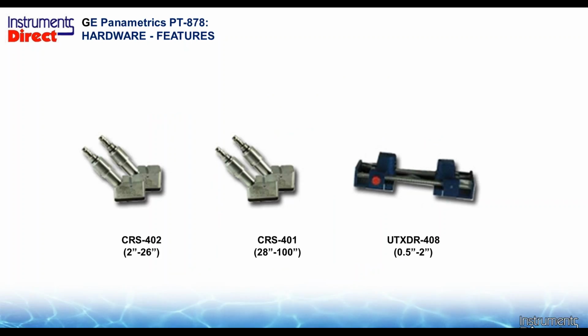Transducers, we have a host of different transducers for this particular model, and the transducers are selected primarily by pipe size. And I think that's a defining point between the PT878 and the bargain brand meters that you can get from other countries for $2,000. This is the difference between the men and the boys here: multiple frequency transducers. Most of the budget price transit time flow meters are one frequency, usually around 1 megahertz, which doesn't work at all on small line sizes. And then the signal processing is not nearly as sophisticated as the PT878. The accuracies aren't on the same page, so it's not an apples-to-apples comparison there.